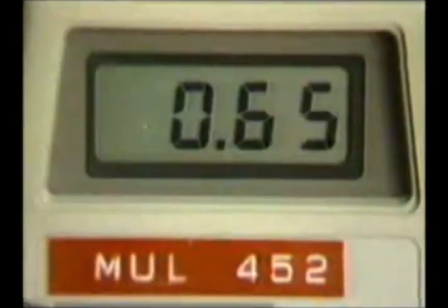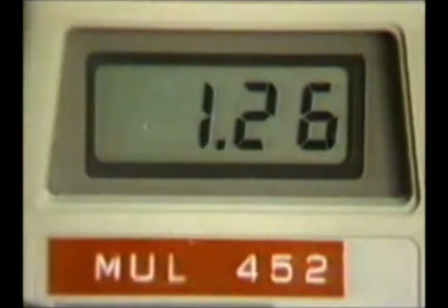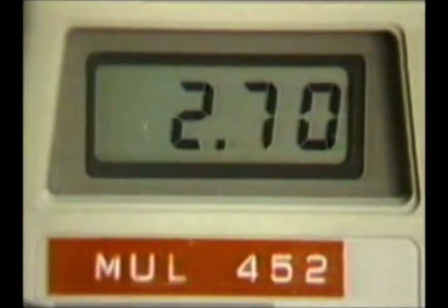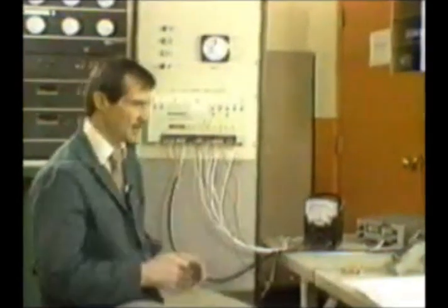and watch my load gain voltage. So as I load up, I should measure around 4 volts, and I do. I measure just above 4 volts. So that tells me, yes, my CTs were hooked up correctly, and so I can go ahead, stop my prime mover again, and hook that A phase back up.